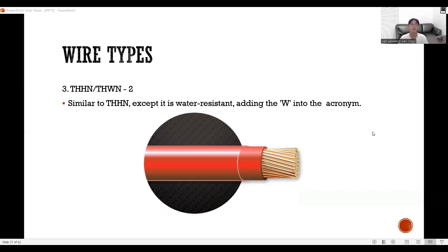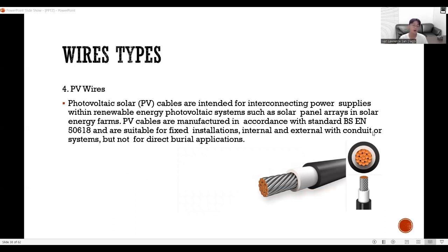Next is THWN-2. Similarly to THHN, except it is water resistant, adding the W into the acronym. And lastly, PV wires or photovoltaic solar cables. It is intended for interconnecting power supplies within renewable energy photovoltaic systems, such as solar panel arrays in solar energy farms. PV cables are manufactured in accordance with standard BS EN 50618 and are suitable for fixed installations, internal and external with conduit or system, but not for direct burial application.